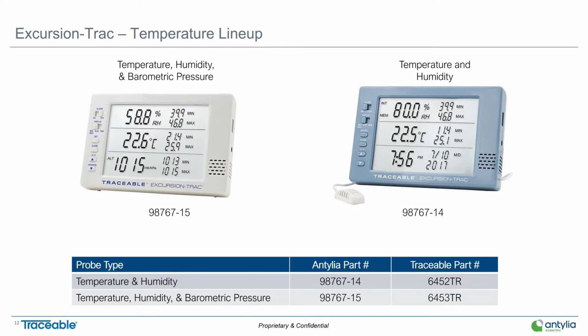One thing I will note for these two is their ambient operating range is bottomed out at 32 degrees. So if you put it in a freezer, which I have seen many people do, the screen will freeze. The device will continue to function, but those crystals are technically liquid and they will freeze in freezers, any environments below 32 degrees. So if it's a walk-in refrigerator, no problem. You put it on the wall, collect all your data. If it is a walk-in freezer or a regular freezer, the screen will freeze. I get quite a few calls on that one, so I always like to bring it up and remind people that the screen is liquid and will freeze. And again, for this one, the Antylia part numbers and the traceable part numbers are at the bottom for your reference.